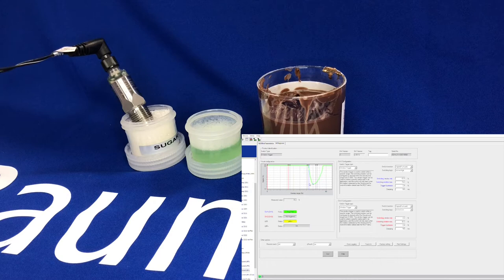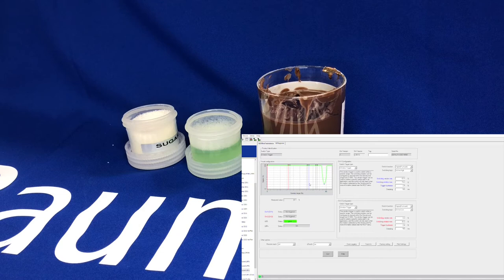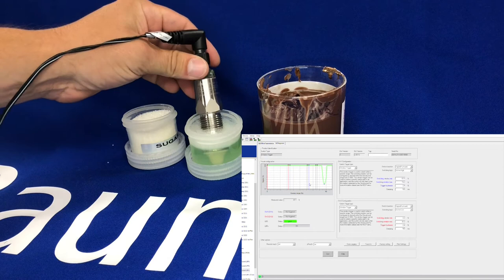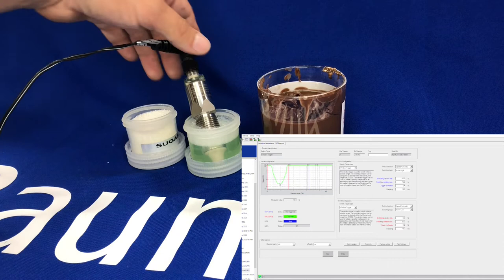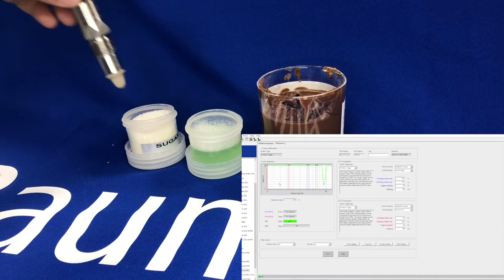It's within trigger one set point threshold windows. If I remove the media, you can now see it's just in there and it's not triggered. If I put it in the water, it'll trigger now on switch point two because that's falling within switch point two's threshold. If I then remove and put it back in the sugar, switch point one is now triggered.